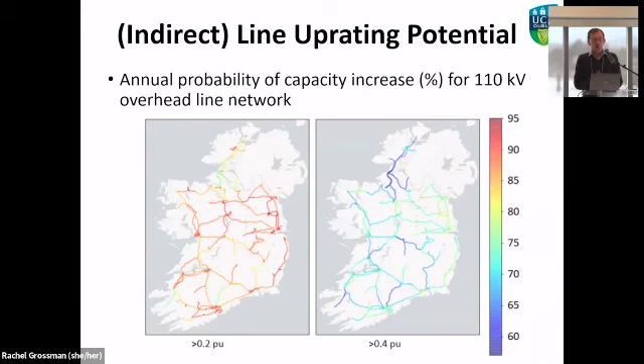Whenever it says greater than 0.2 per unit, the megawatt rating for the line is varying with the time of year. If you aim for a 20% increase, you can see the figure on the left. If you're more ambitious and want a 40% increase, the likelihood of achieving that on a regular basis is obviously lower.